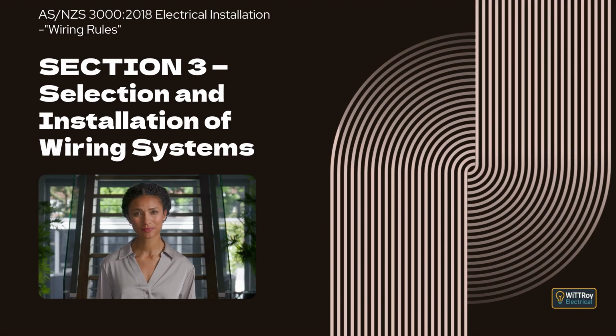where practicable. Covers remain continuous through walls and floors. Trunking is accessible along its entire length, and cables do not rely on removable covers for support. It also explains that non-hygroscopic trunking must be used for insulated, unsheathed conductors, and that live parts of accessories mounted on trunking must be arranged so that basic protection is provided.